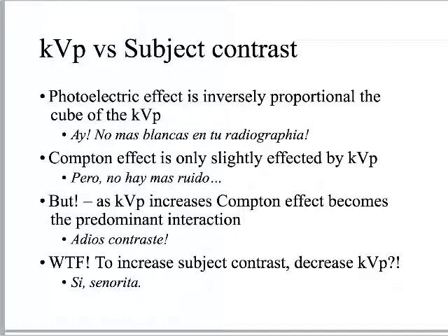If we're honest, if this is guiding treatments, surgeries, detecting cancer — if I can't see what I need to see, I've effectively put the patient at risk. So the counterintuitive question is: to increase subject contrast, you decrease KVP? The answer is yes. To increase subject contrast, you decrease KVP. I will say that over and over again. It is one of the most counterintuitive things about x-ray. If I want to increase subject contrast, I will decrease KVP.